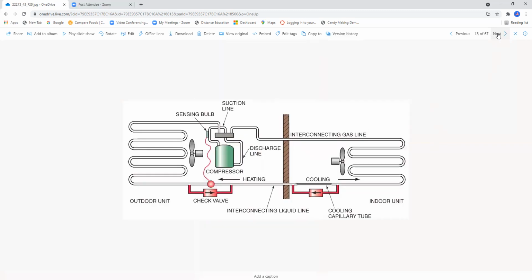In this particular illustration, which is also found on 1285, this one here utilizes a capillary tube for, that's interesting, it uses a capillary tube for the indoor cycle and a TXV for the outdoor cycle. So that's kind of interesting. So we have two metering devices, one for the outdoor section, one for the indoor. So a cooling capillary tube for the cooling cycle. Then for the heating, they're utilizing a TXV. I honestly have never seen one of these.